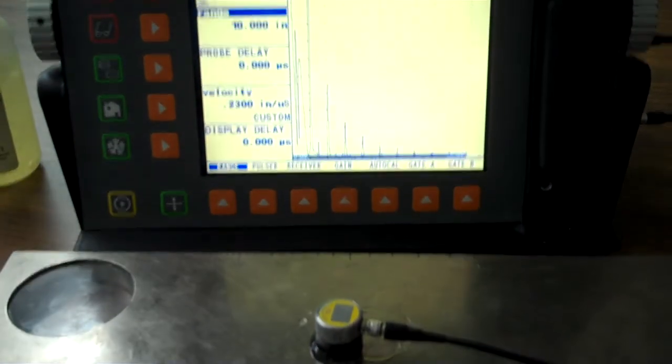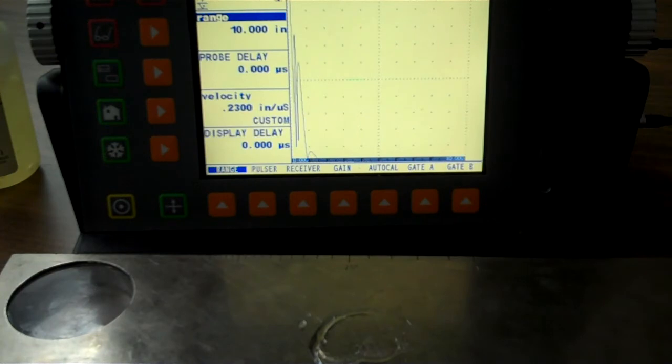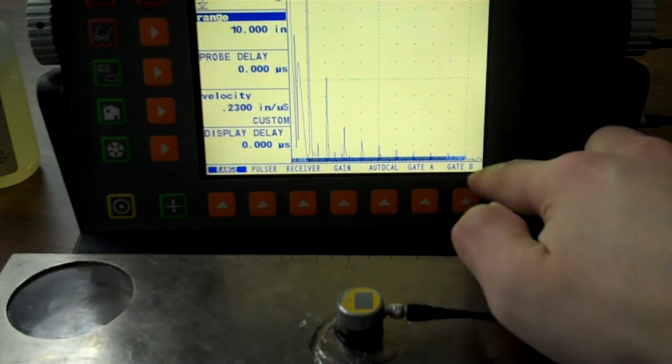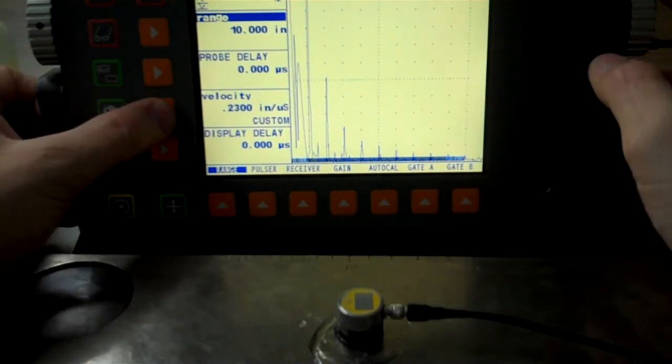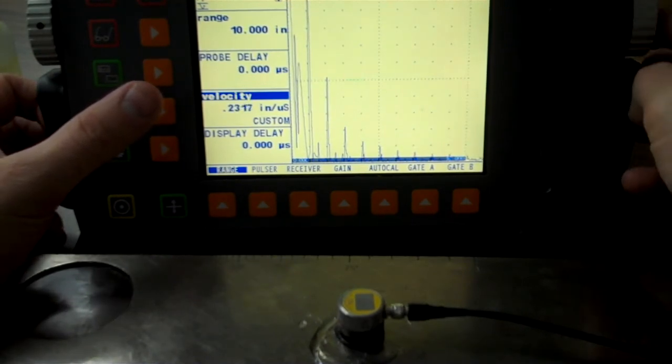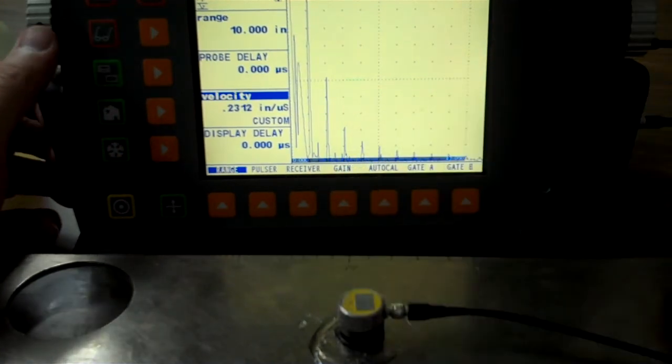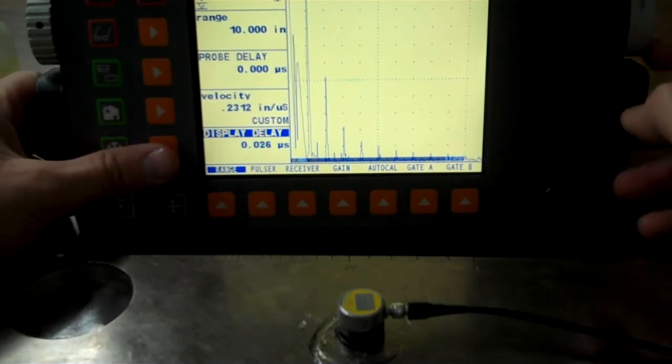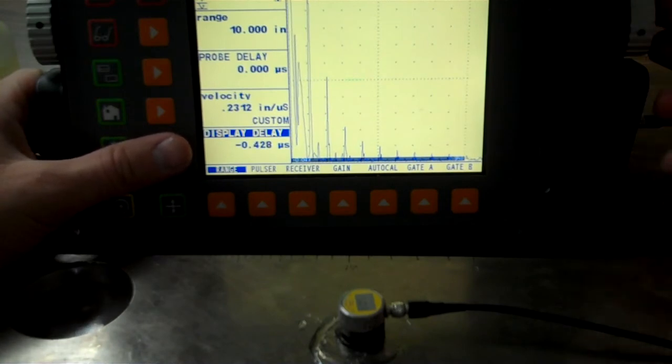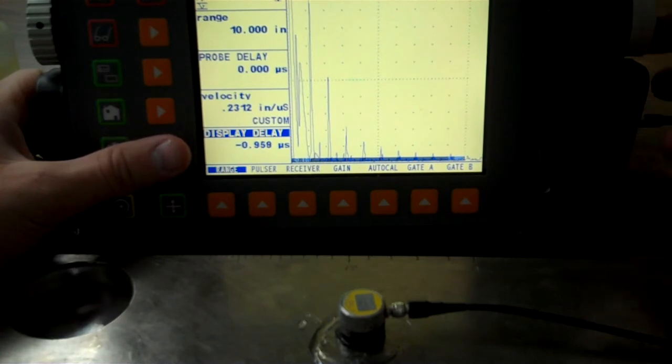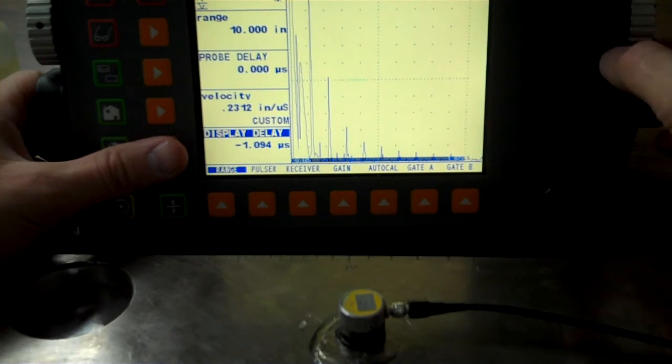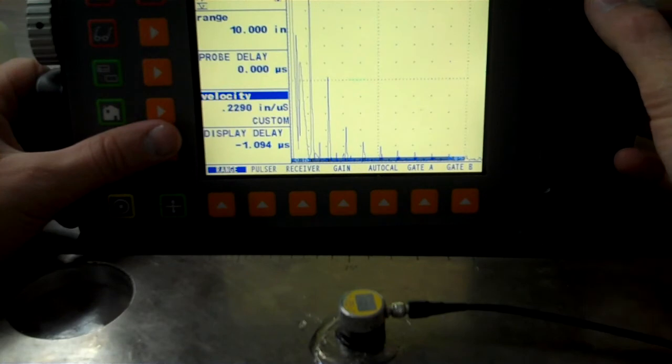So if we're on a 10 inch screen range, you can see my transducers down on the IIW block. Back up a little bit so you can see that. That's just how it's setting. If I pull the transducer up, let it refocus there, signals are all gone. Plug that guy down on there, and now I've got my signals, 1 through 10. They're not perfectly lined up, so I want to line them up a little better. I'm going to do that by fine range, or in this case, velocity. So we're close, we're not necessarily perfect. I'm going to push this over just a little bit. I'm going to come back to my velocity, put them about right there.